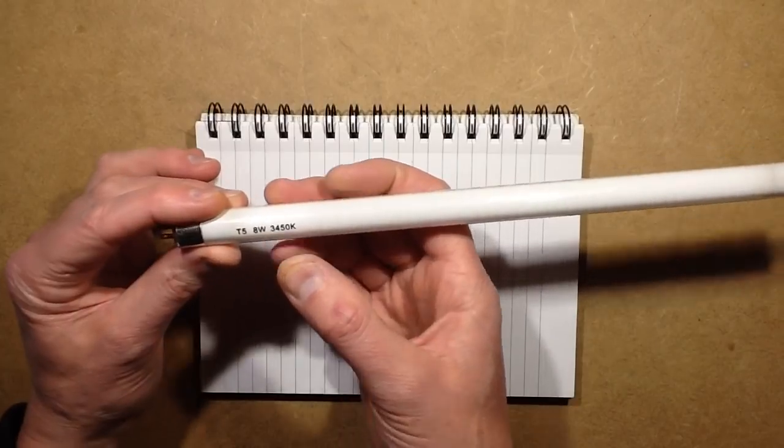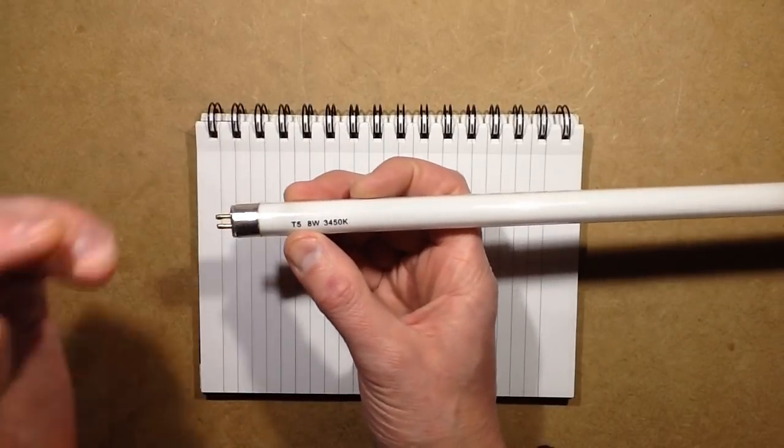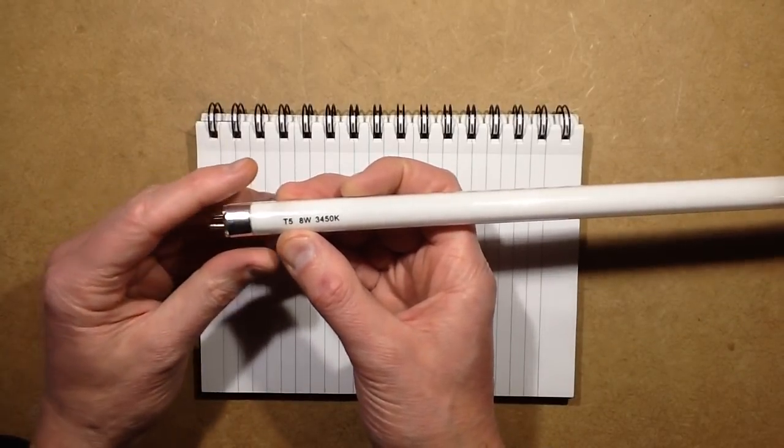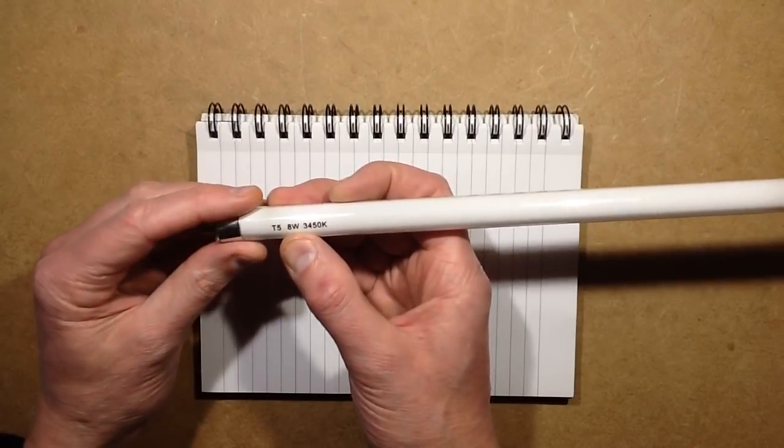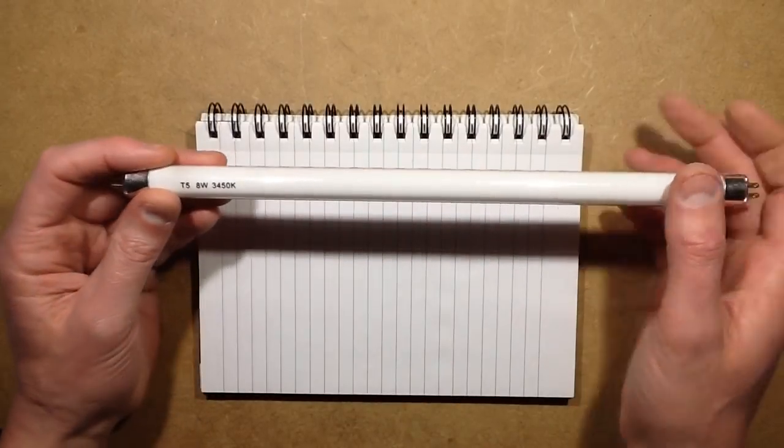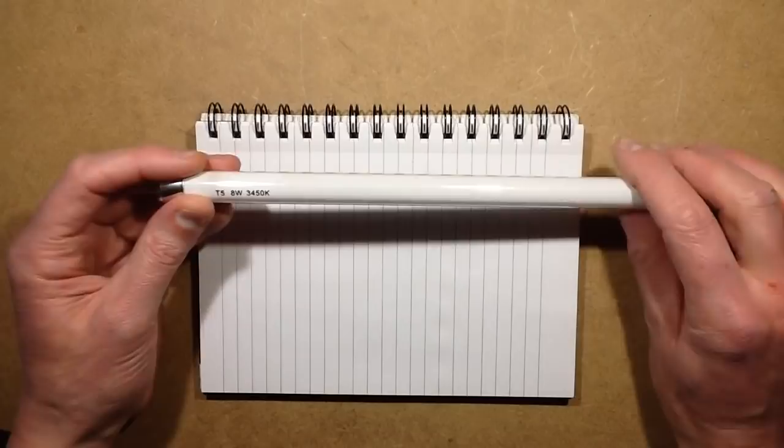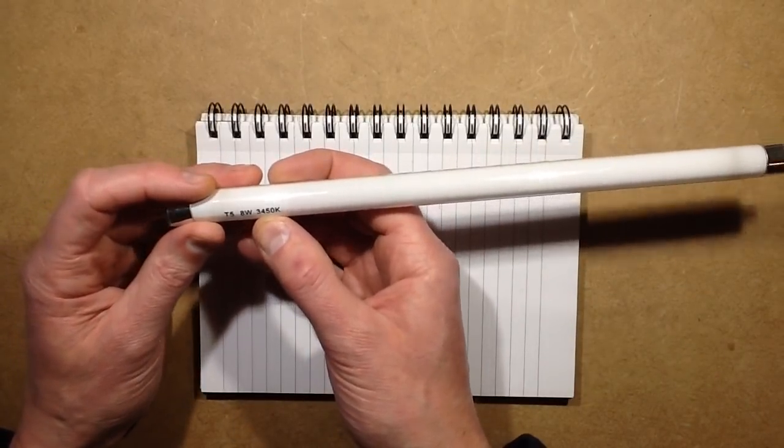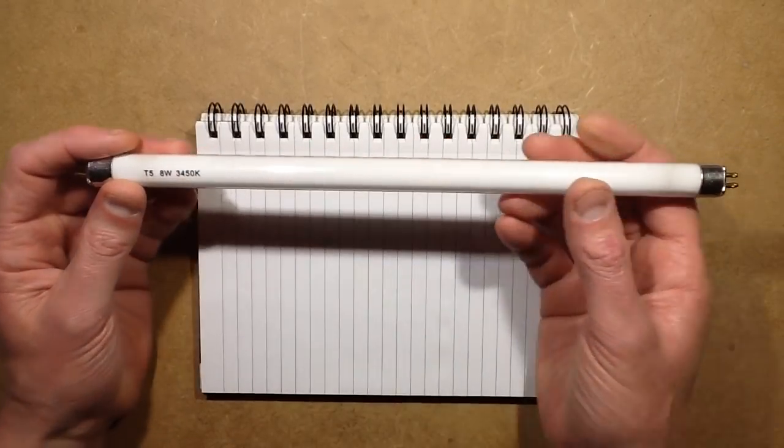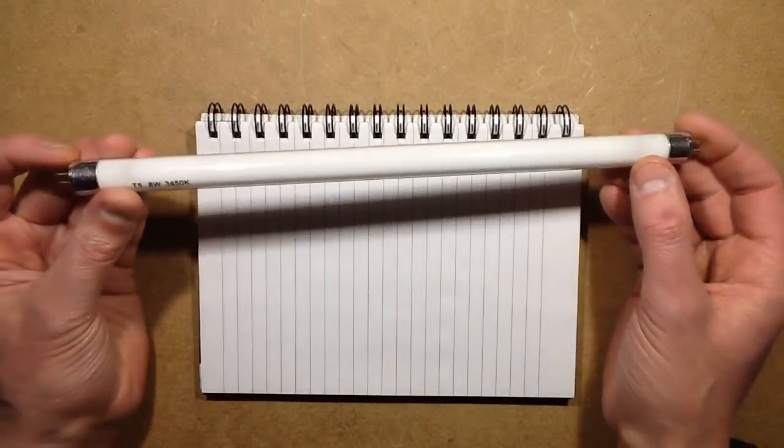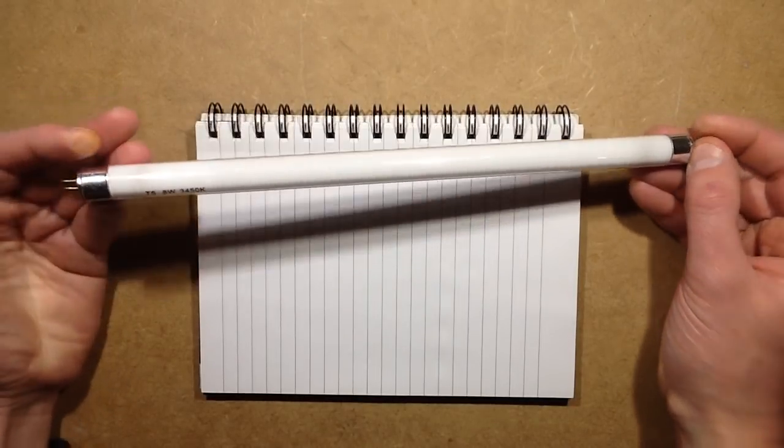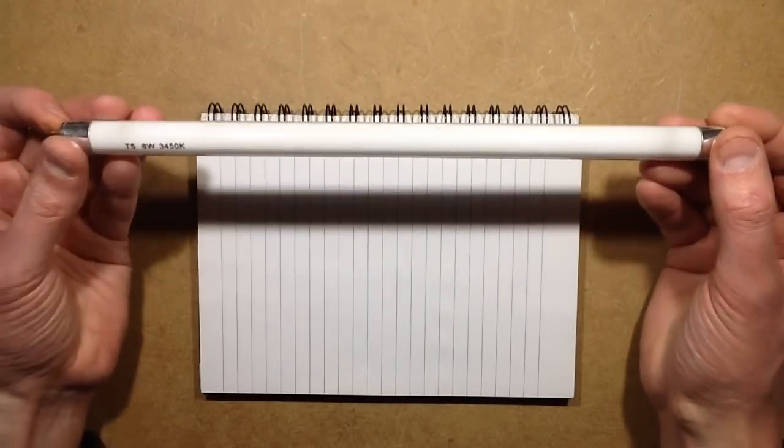So this is a T5 8-watt tube. The T5 is the diameter in eighths of an inch. The 8-watt is its power rating of the tube itself, not the driver and ballast. The 3450 is the color temperature, which is fairly warm white. Now you'll notice that this fluorescent tube has two pins at the end. You do get a type of tube called an instant start, which is a single pin. It's actually a cold cathode tube. These are hot cathode tubes, and to explain that, I have to draw it.